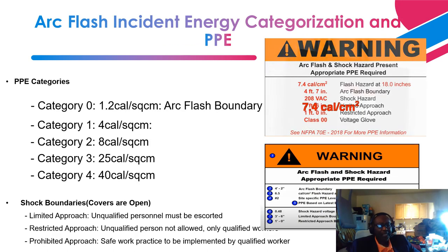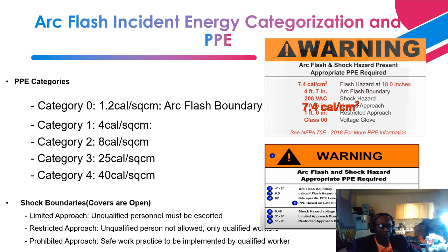Now let's talk about Arc Flash incident energy categorization and required PPE. After completing all modeling and simulation — first the short circuit simulation, then the Arc Flash analysis — you categorize based on incident energy. Category 0 is up to 1.2 cal/cm², Category 1 is up to 4 cal/cm², Category 2 is up to 8 cal/cm², Category 3 is up to 25 cal/cm², and Category 4 is up to 40 cal/cm². Based on your simulation results, if your incident energy is less than 4 cal/cm², your PPE categorization is Category 1.